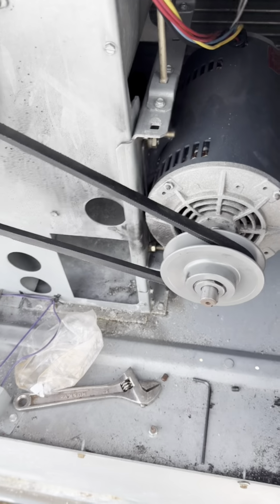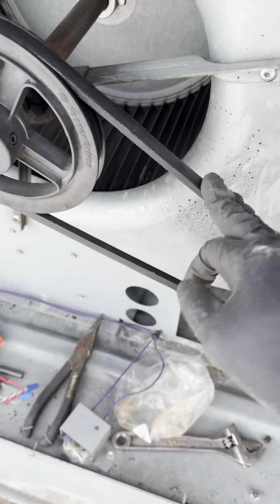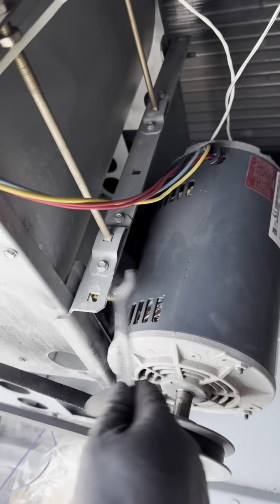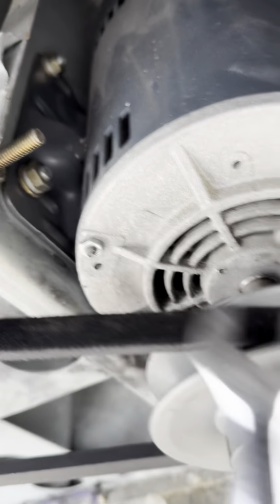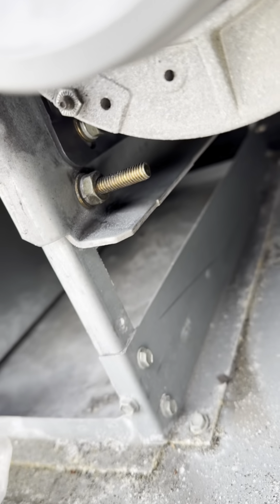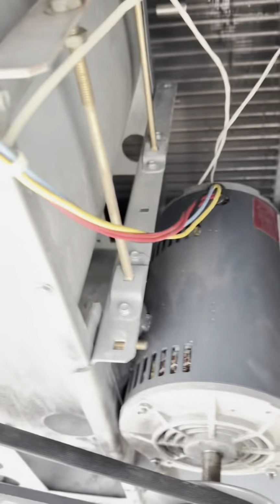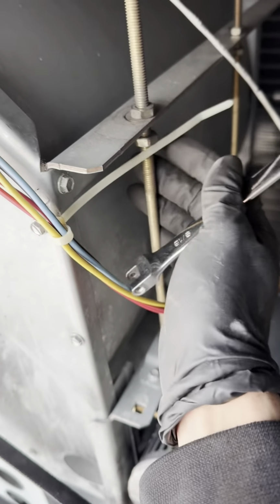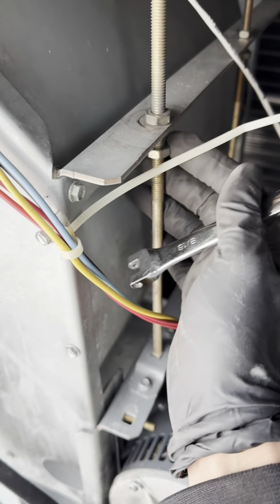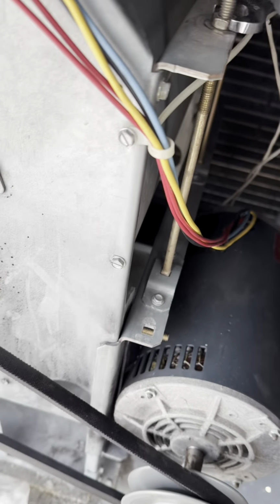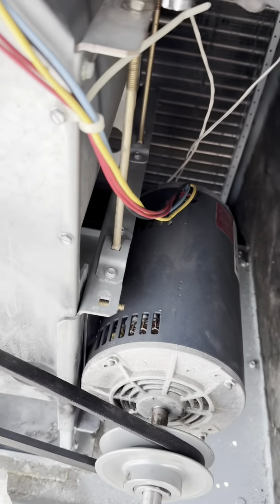All right, motor pulley's on. Now we're adjusting the belt tension. To do that, you loosen these 4 bolts that are holding the motor bracket in place. There's 4 of them, 2 in the back, 2 in the front. And then with these adjusters, you'll loosen the nut underneath and continue with a 9/16 wrench. Tighten them both the same way. Make sure you don't go one more than the other, because then you're picking up the motor not evenly.